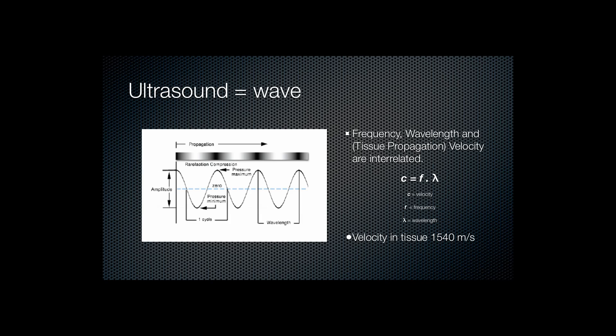The frequency, the wavelength, and tissue propagation velocity are interrelated as shown by the equation at right. In particular, the velocity in tissues is defined as a constant. It's assumed to be 1,540 metres per second, and for most of the soft tissues of the body that holds true with minor variations.